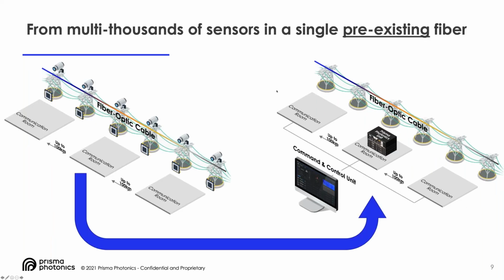How is it done, since eventually we need a sensor? The beauty is that we can use the pre-existing fiber, the OPGW, as our sensor. So the whole installation is placing the PrismaPower system in an existing communication room and plugging it into a pre-existing fiber. That's the whole installation. Once done, a single system can cover 100 kilometers without installing anything on the towers themselves.